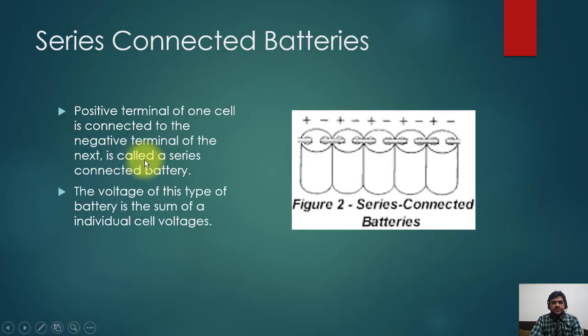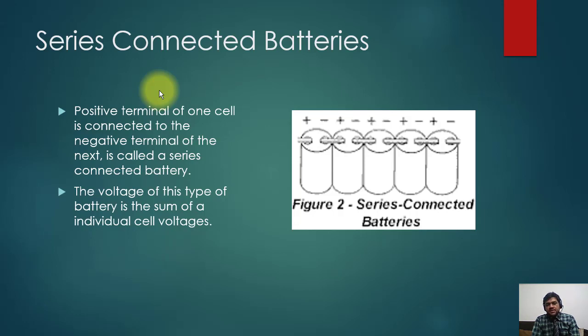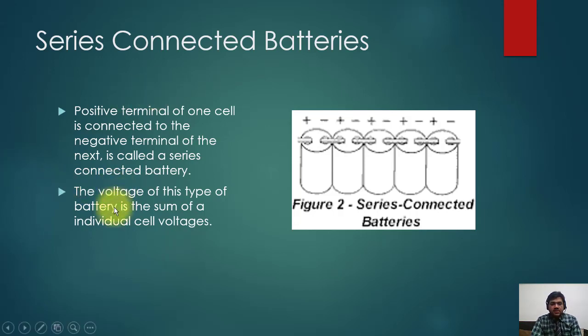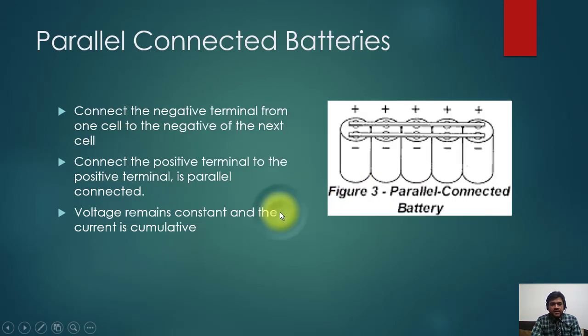In maintenance, you must continuously check the battery's specific gravity. If it goes below a certain level, the charging is not healthy and you should check your charger. You can also connect batteries in series. In series connection, the voltage increases and you get more voltage, but the current capacity remains the same. The positive terminal of one cell is connected to the negative terminal of the next. The total voltage of the bank is the sum of the individual cell voltages.